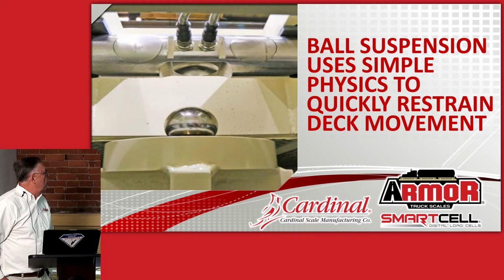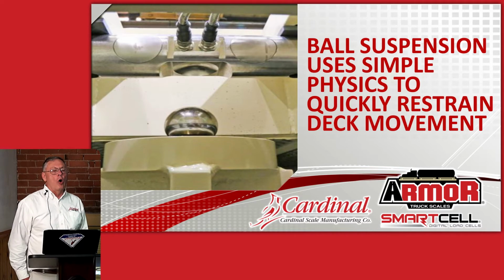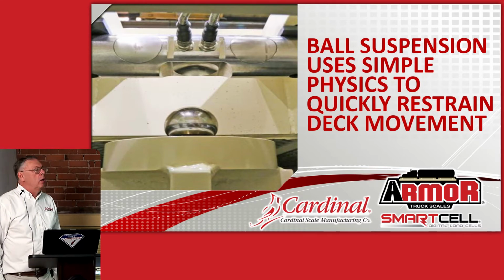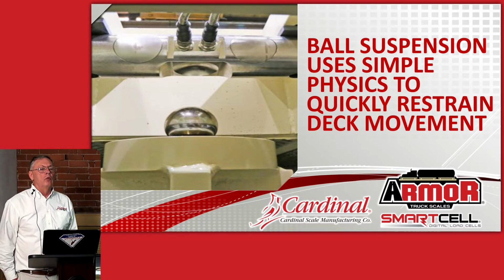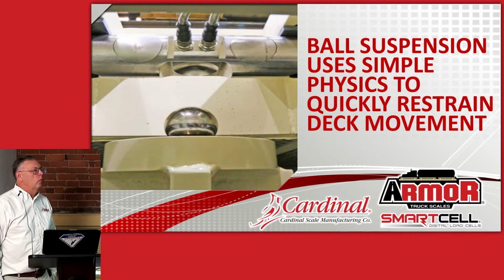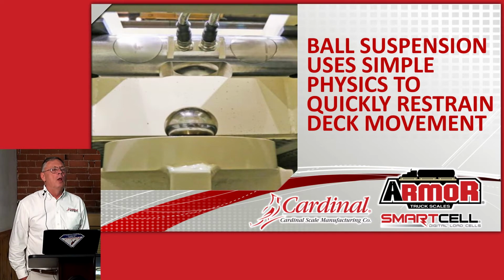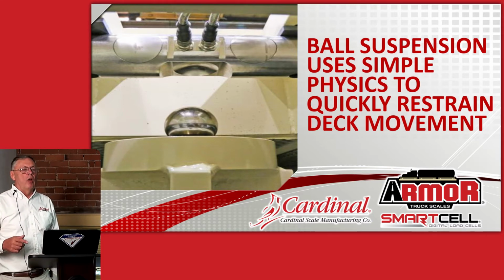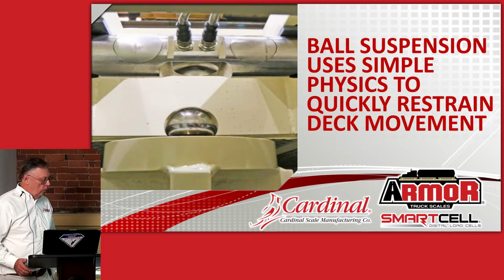Now, in that photograph, you can see between the weighbridge and the load cell, we've got a hardened bearing plate that sits there. If you need to shim one of the load cells to get the dead load the same on initial installation, we ship shims, where you can just loosen the bolt on the load cell. It doesn't have to be completely removed, and you slide a shim in there to bring your dead load readings up.